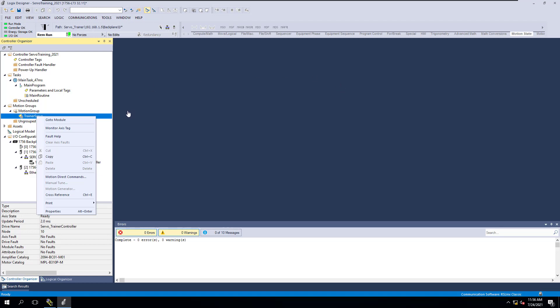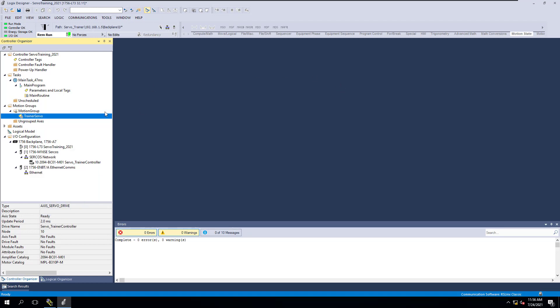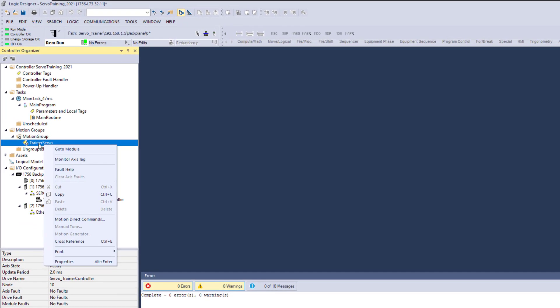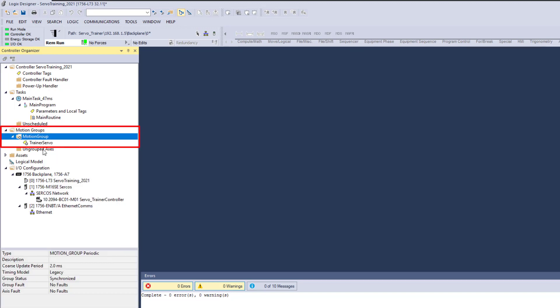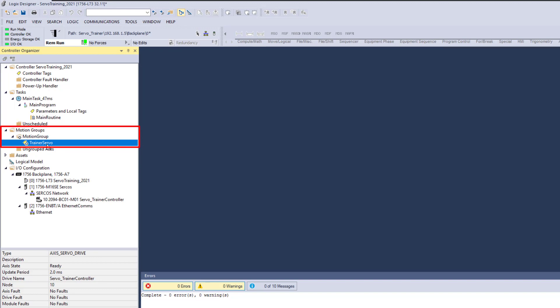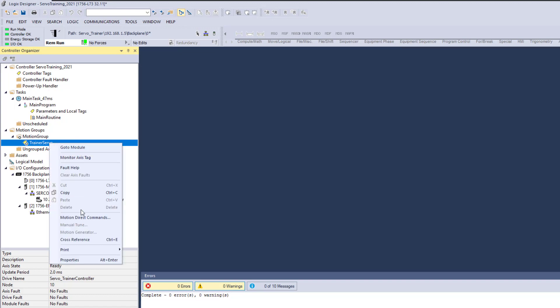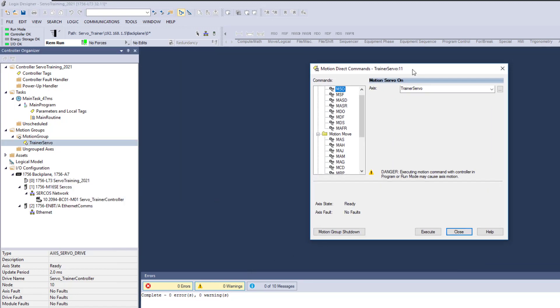One implementation I'll show you: motion direct commands are accessed by going to the actual servo you want to control. In this case, we go to our motion group — the servo is right here. This is in Studio 5000 version 32. This servo happens to be a Kinetix 6000, but you can do this on all the series of Kinetix drives that exist inside of Rockwell Automation — it could be a 5700 or a 5500. So I'm going to right-click and go to motion direct commands.